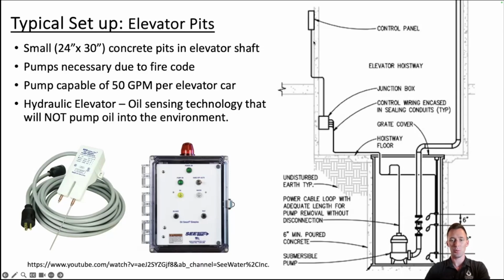They're typically paired with a control panel. Sometimes we see drawings where it's a single float that's actuated up and down. That really eliminates the chance that you have a way to test the pump, to make sure it's still working. It eliminates alarms. So a control panel would be the way to go. So you get an alarm, you get the ability to test the pump. You also have a building management system. Dry contact hookup is typical for the sump pump category. So you get dry contacts within the panel to hook to your building management system. It can tell you if this pump's turning on. So a control panel, we kind of view that as a must.